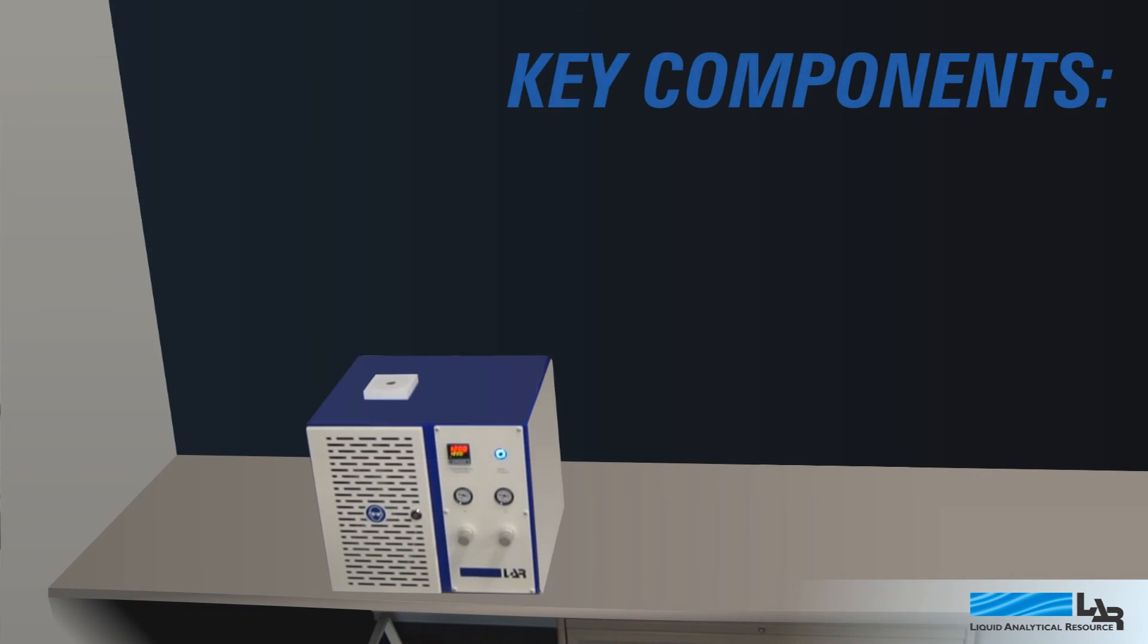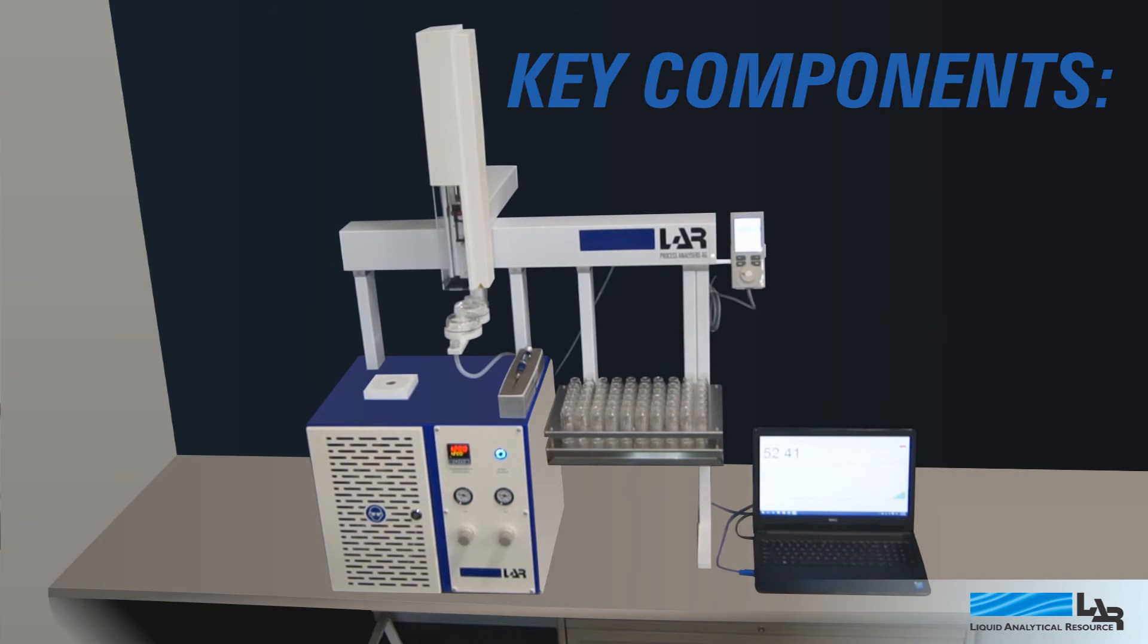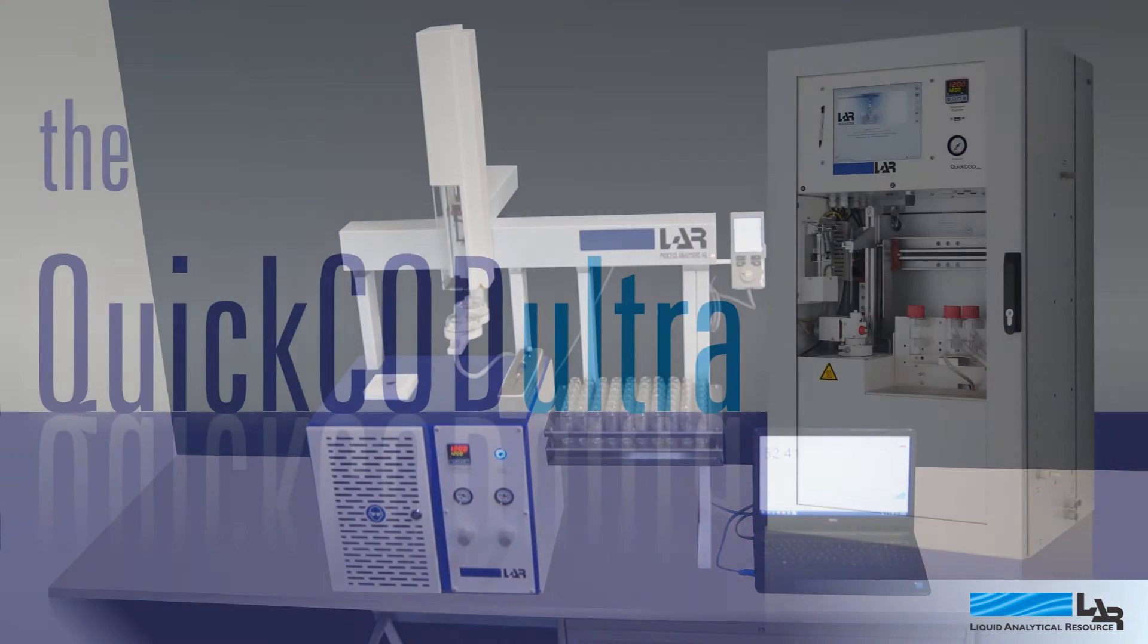The TOD measurement method has now been automated for laboratory use with the QuickCOD lab. Using combustion at 1200 degrees C, the QuickCOD lab operates under the same principles used for many years in hundreds of installations by the online QUIC-COD Ultra.